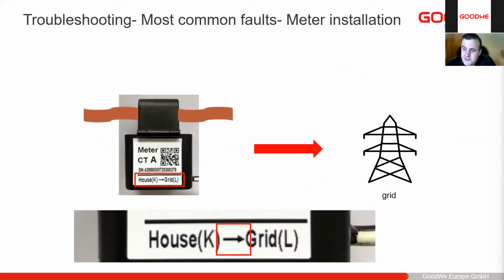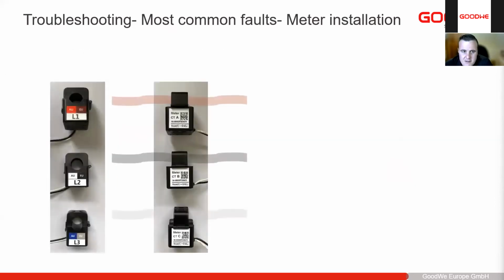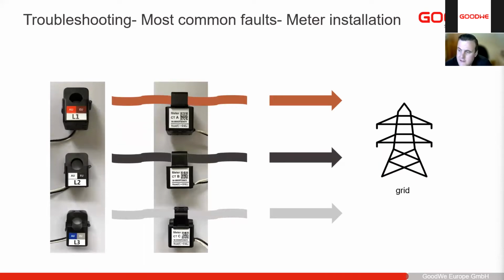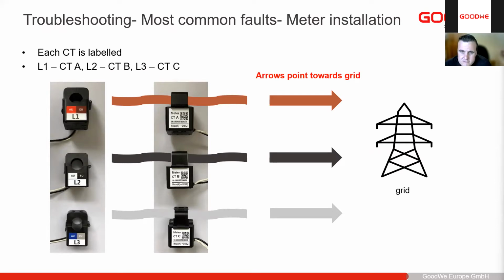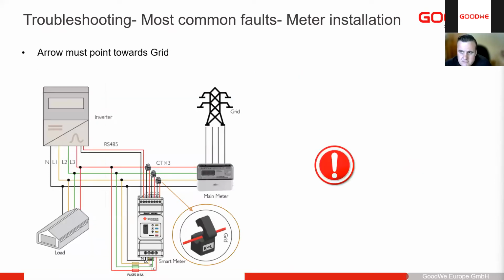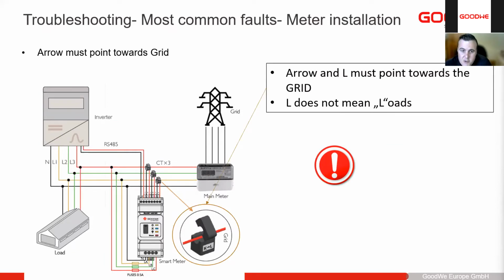Next is our CTs. On our CTs we have an arrow. I have never ever had this be incorrect on any one of our CTs. So please always try to install it with the arrow in the correct direction, house to grid, towards the utility. Because if we know our CTs are correct, and we see the arrow direction is correct, then we need to fault find in a different area to find where our problem is. Same with three phase, A, B, C, we always have that K to L. So K is the house, L is the grid. So L always points towards the grid. L is not the load. K to L.